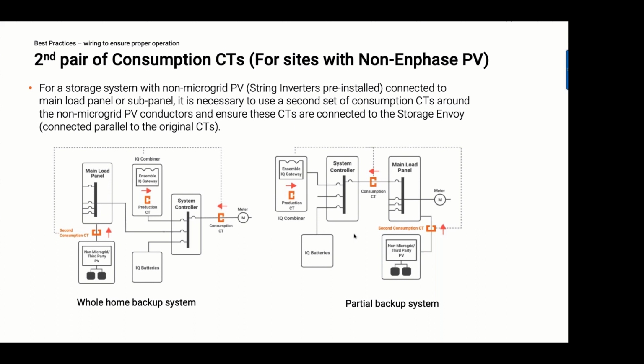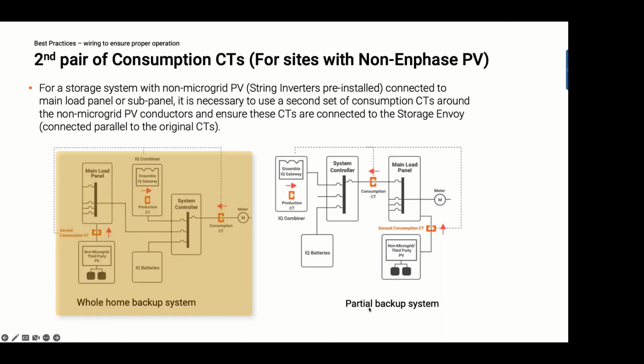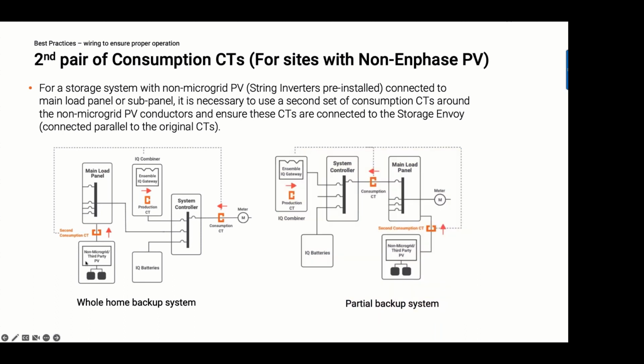The next best practice is related to having a third-party PV within an Enphase energy storage environment. We do support systems where you have third-party PV that's outside of the microgrid. So I've got 2 pictures here. One is a whole home backup system. The second one is a partial backup system. And we've called out that there is a third-party PV that's not in the microgrid, right? And this is how you have to do it. If you have third-party PV like SMA or Fronius or SolarEdge or something like that, and you want to integrate this into an IQ battery system, then this PV has to reside outside of the microgrid.